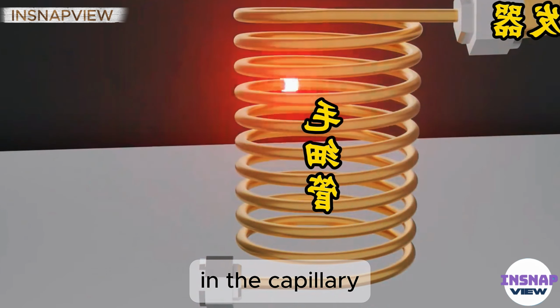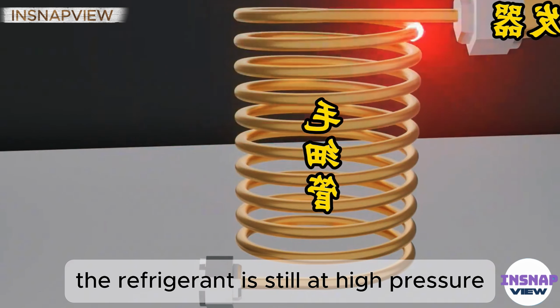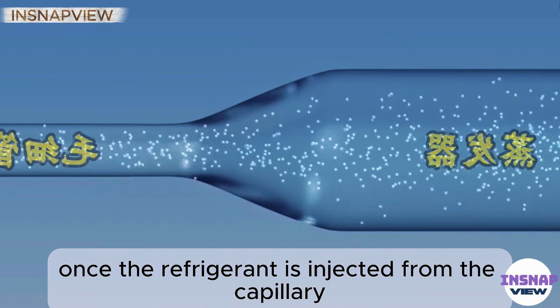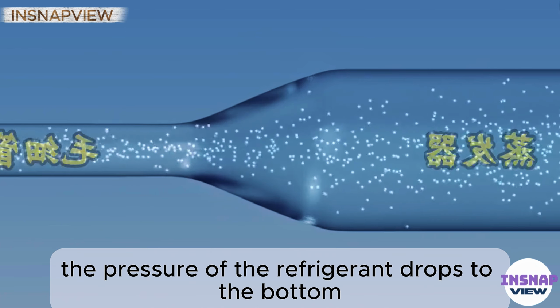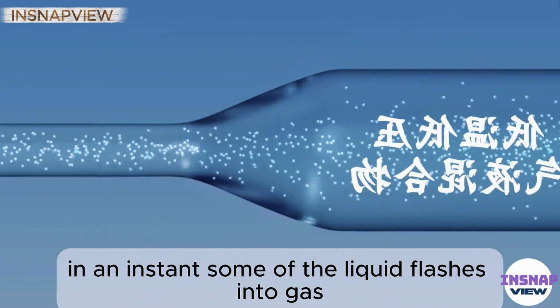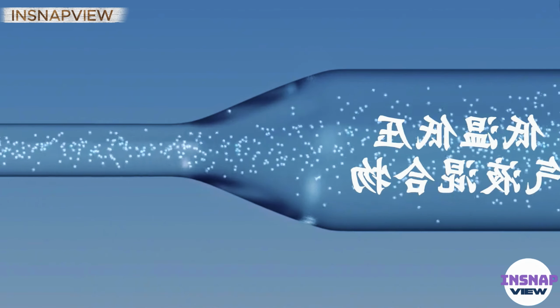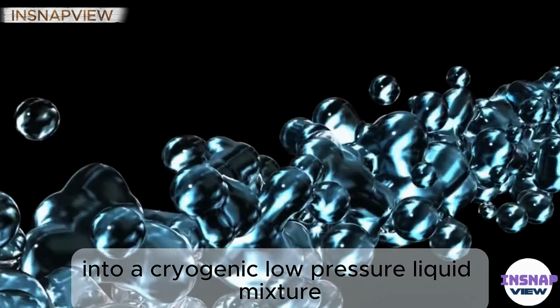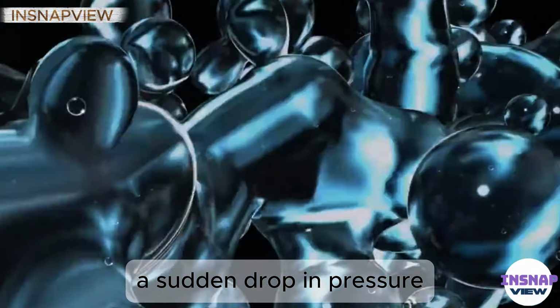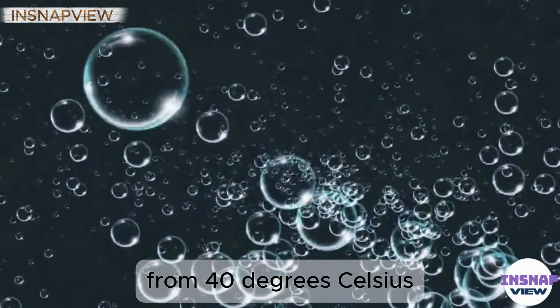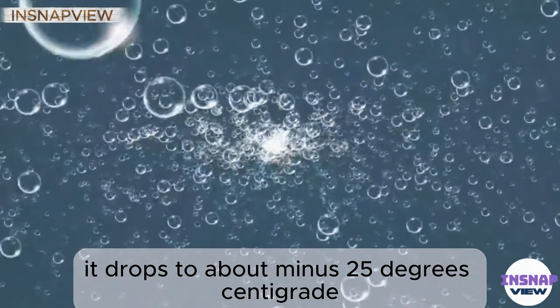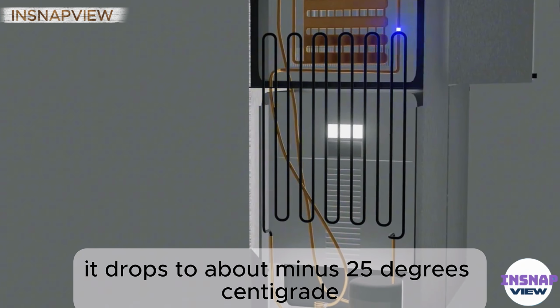This makes the depressurization process gradual and not a sudden jump. In the capillary, the refrigerant is still at high pressure. Once the refrigerant is injected from the capillary into the evaporator, the pressure of the refrigerant drops to the bottom in an instant. Some of the liquid flashes into gas, becoming a cryogenic, low-pressure liquid mixture. A sudden drop in pressure makes the temperature of the refrigerant drop from 40 degrees Celsius to about -25 degrees Celsius.